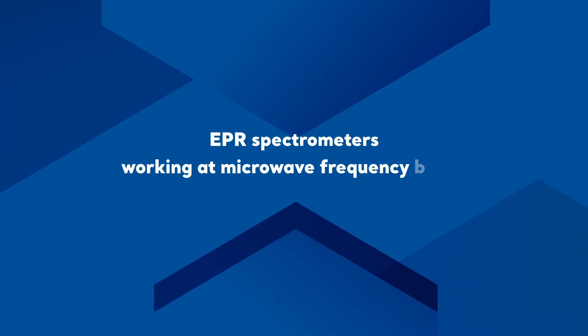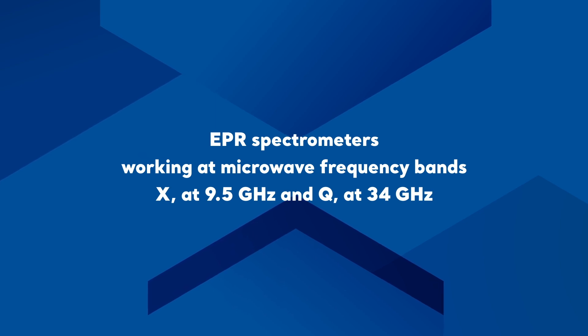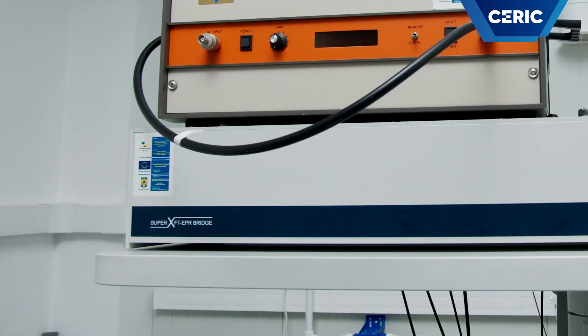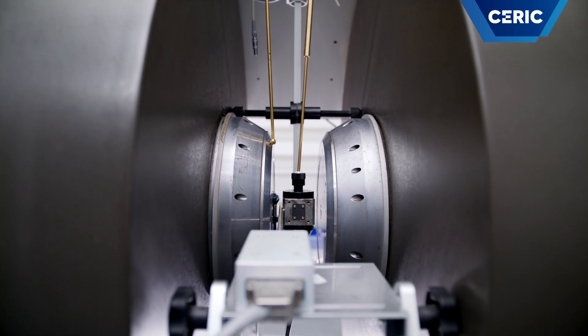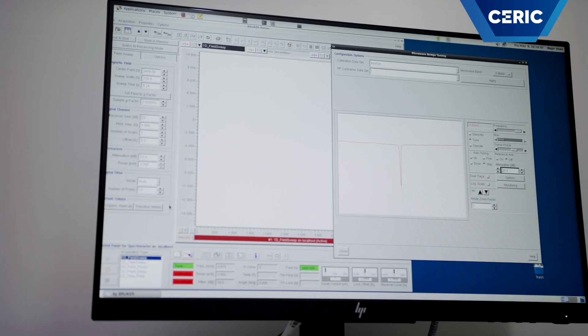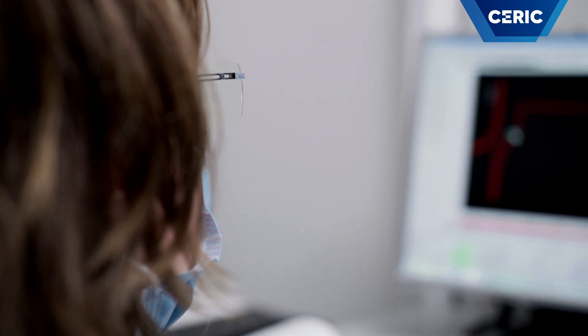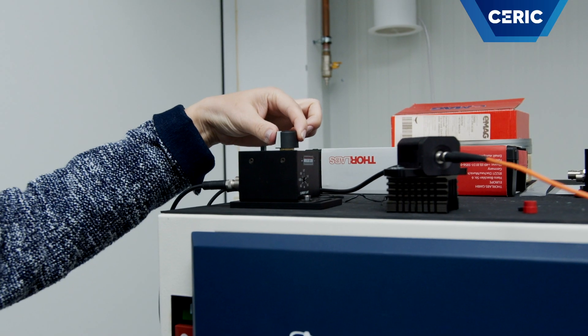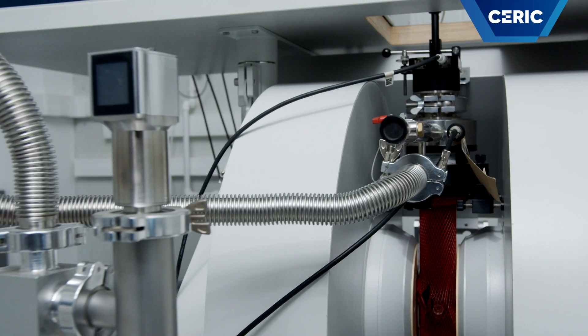Our laboratory is equipped with EPR spectrometers working in the microwave frequency bands X at 9.5 GHz and Q at 34 GHz. The EPR spectrometer consists of a source of microwave radiation, a resonant cavity into which the sample is inserted between the poles of the electromagnet that generates the magnetic field, and a detector to measure the microwave signal reflected from the cavity. The microwave frequency is constant while the magnetic field is scanned. The microwave absorption signal is recorded as an EPR spectrum. Depending on the samples and the information required, the experiments can be performed at one or both microwave frequencies, at variable low temperature, or with in-situ illumination.